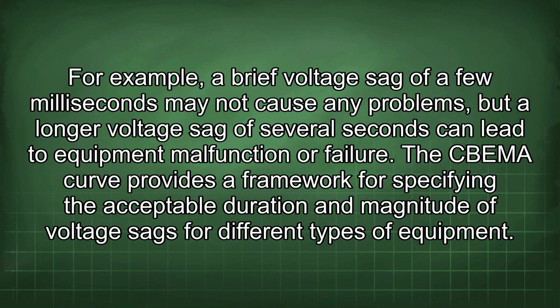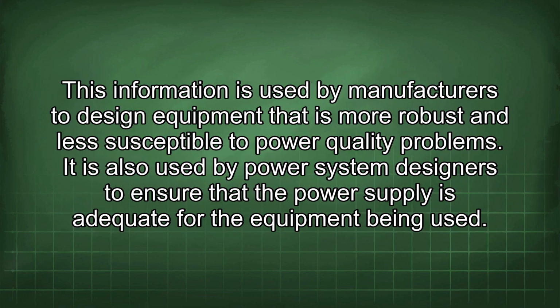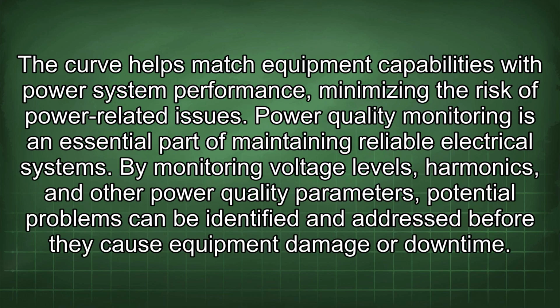The CBEMA curve provides a framework for specifying the acceptable duration and magnitude of voltage sags for different types of equipment. This information is used by manufacturers to design equipment that is more robust and less susceptible to power quality problems. It is also used by power system designers to ensure that the power supply is adequate for the equipment being used. The curve helps match equipment capabilities with power system performance, minimizing the risk of power-related issues.